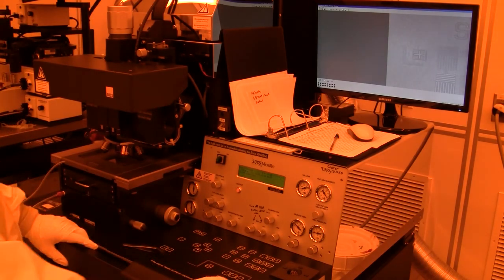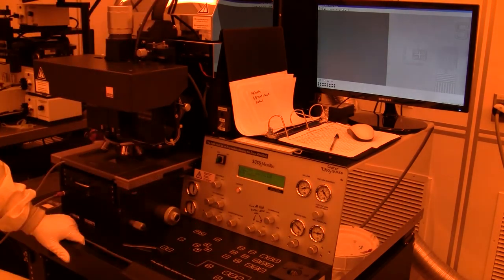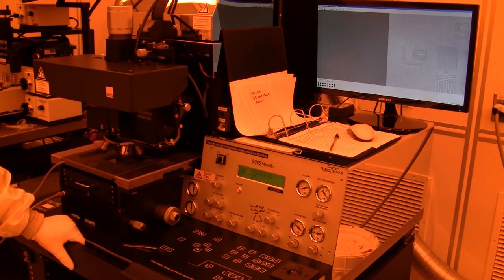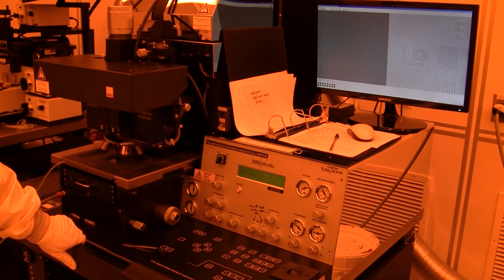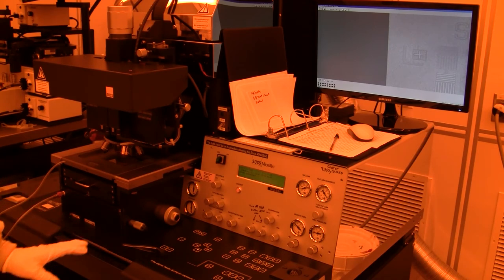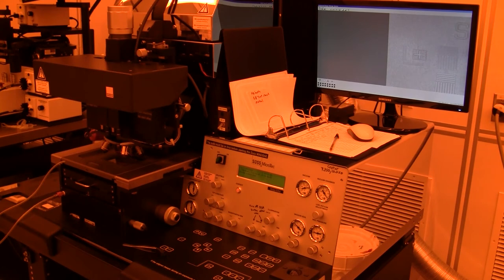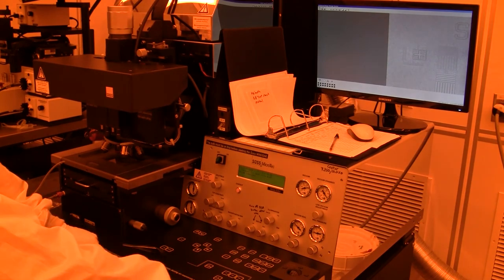The lamp is held at constant power. As it ages, the tool provides more electrical power to maintain constant brightness - optical power, optical flux, I guess, the milliwatts per square centimeter. So it maintains a constant flux by adjusting the lamp power.